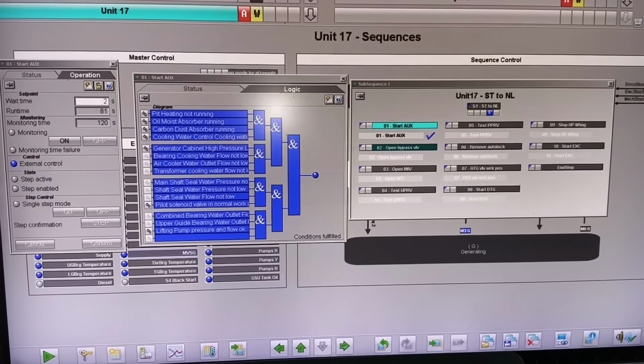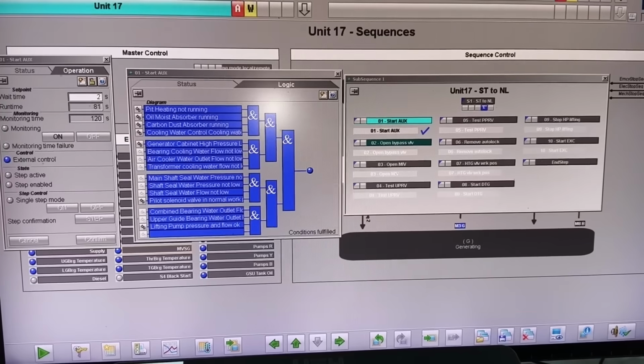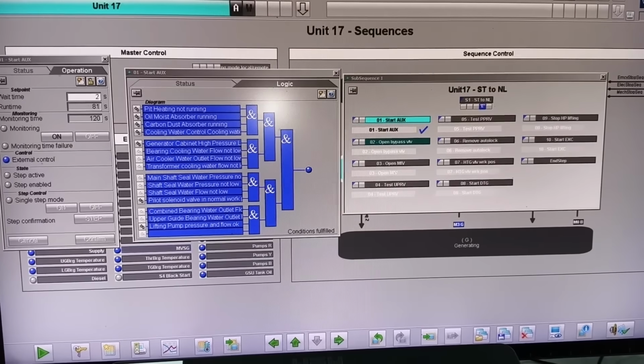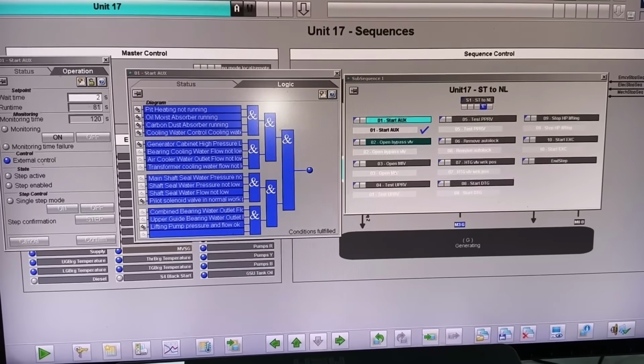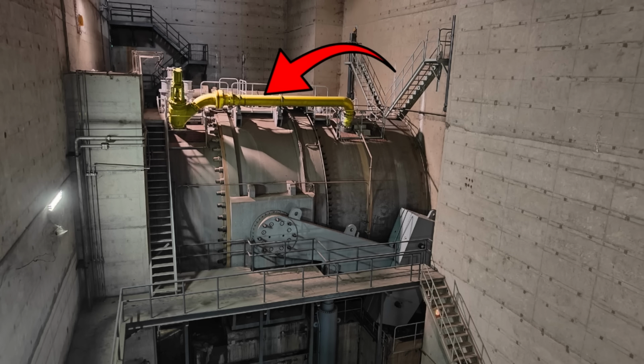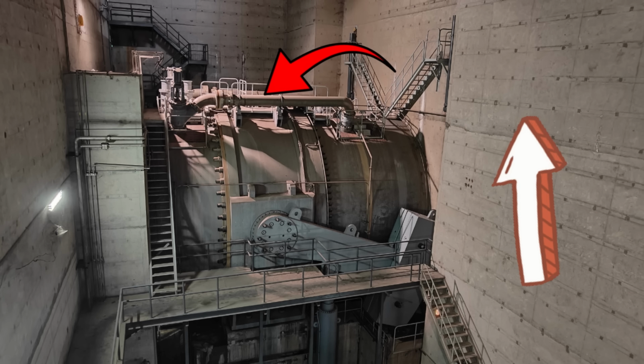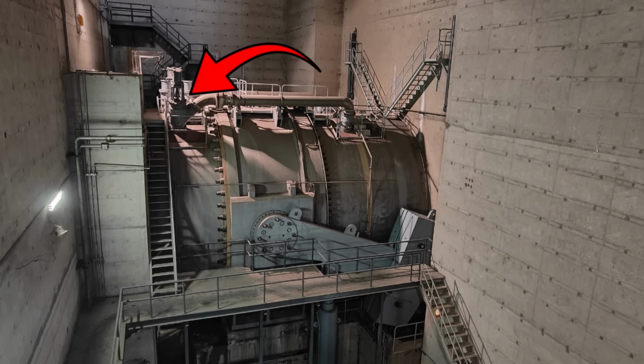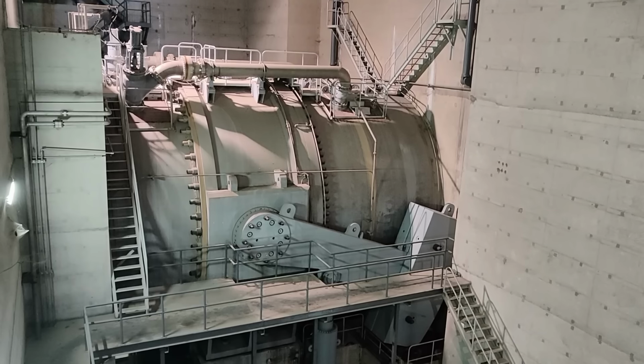As you can see on the screen, the system now enters step 2, which is opening of bypass valves. This valve opening is very important for equal pressure. You can see full details about this bypass valve here. I have highlighted the motorized valve of the bypass pipe here. Keep an eye on this motorized valve as they begin opening, and listen carefully to the sound of filling water.